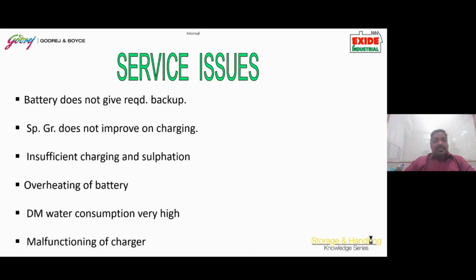In such cases, if the entire battery is not giving backup, our service team normally takes the battery to the service station. We remove the complete acid, put in new acid, recharge it as per the SOP, and then do 3, 4, C5 backup tests to ensure the positive plates are fully charged, have achieved their capacity, and all sulfation has been lost. This is one method by which we revive batteries.